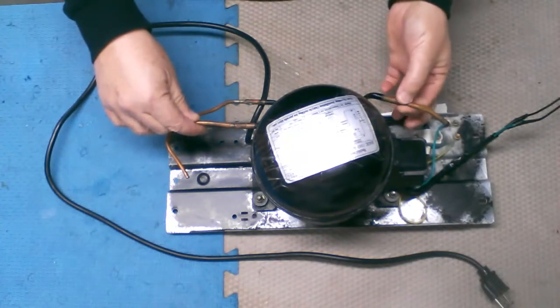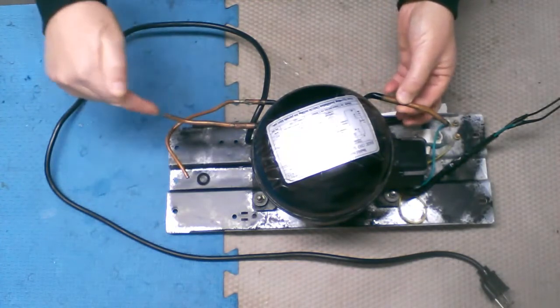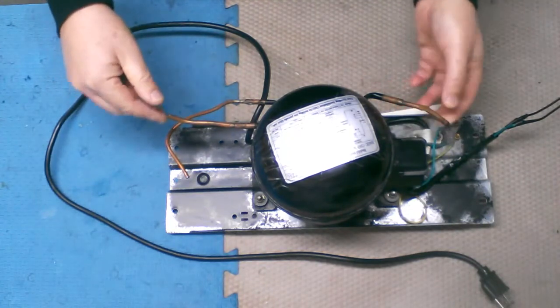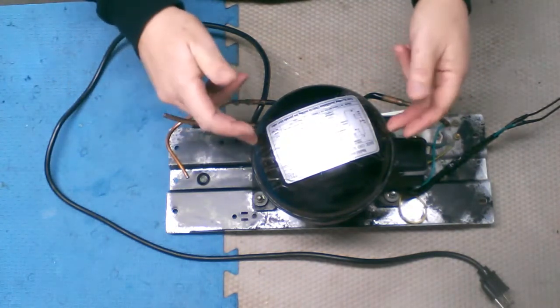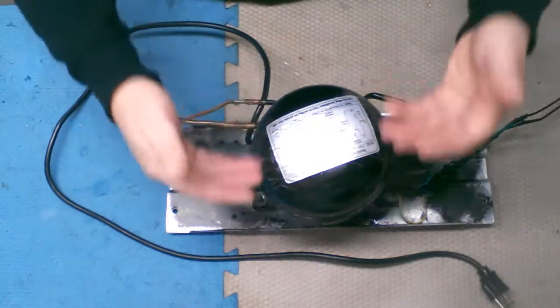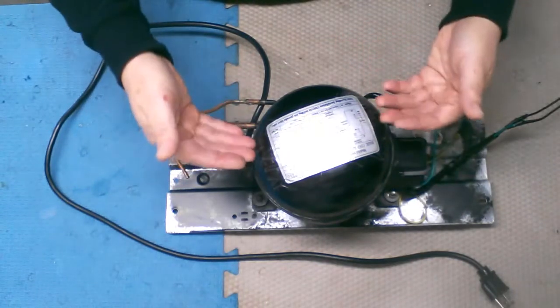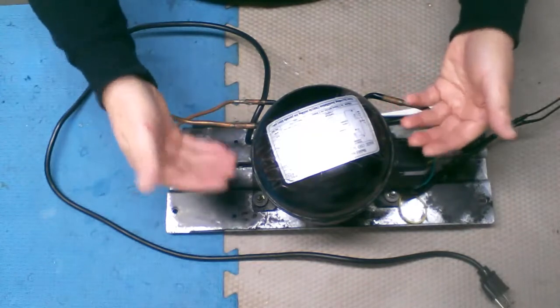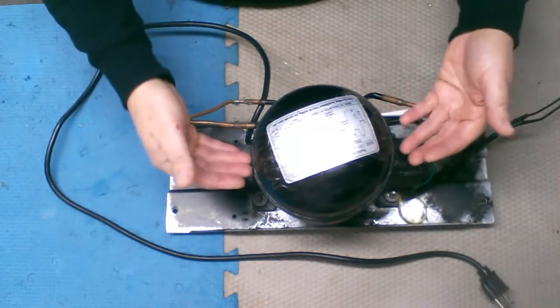You can cut this off over here and drain out the oil inside the compressor and pump in new oil, but then you're going to have to close this up again. You can do it right through the inlet side on this side as well. That's what I did. Because you want to drain out the oil that is in there. The oil that is in there has been contaminated by the Freon. The Freon and the oil and everything all works together. So you want to drain out the old oil and put in new fresh clean oil. That way you're going to prolong it and make it run better.